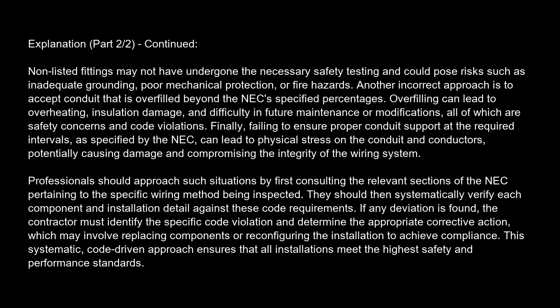Another incorrect approach is to accept conduit that is overfilled beyond the NEC's specified percentages. Overfilling can lead to overheating, insulation damage, and difficulty in future maintenance or modifications, all of which are safety concerns and code violations. Finally, failing to ensure proper conduit support at the required intervals, as specified by the NEC, can lead to physical stress on the conduit and conductors, potentially causing damage and compromising the integrity of the wiring system.